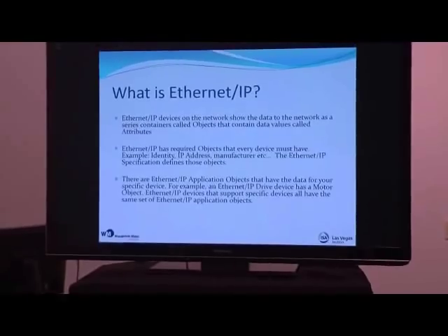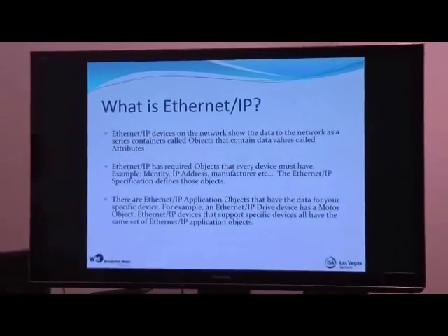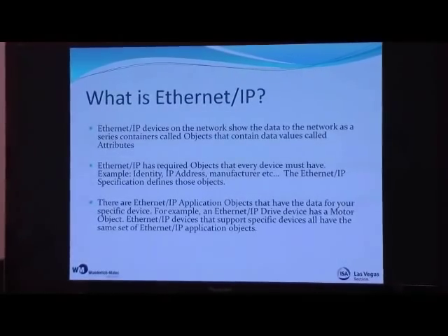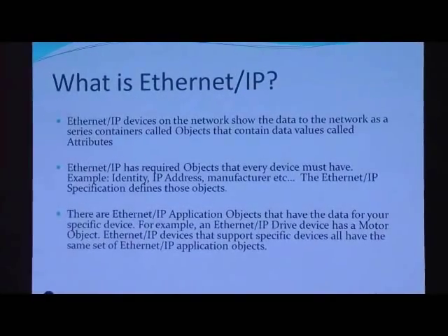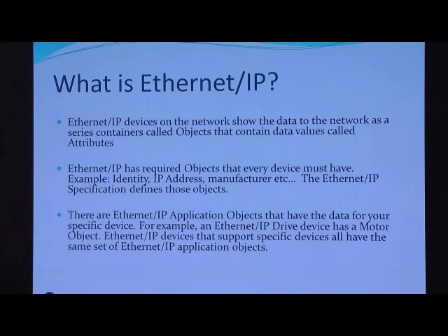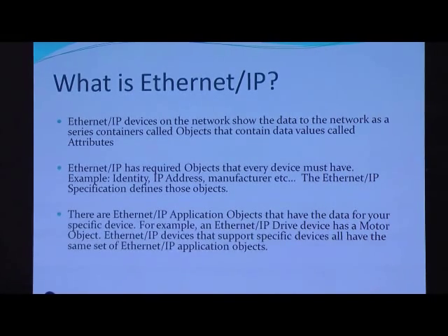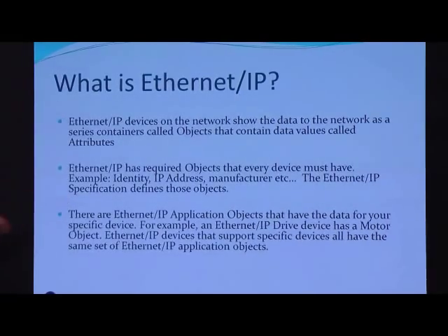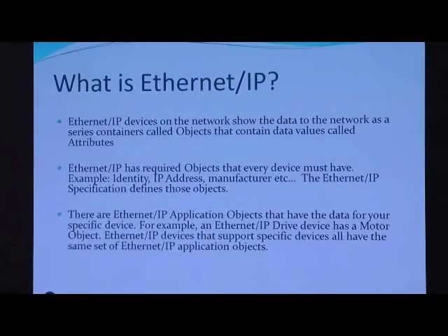Another important piece of information about Ethernet IP is that the specification requires vendors to encapsulate their data in objects. Objects contain the individual values of the device as attributes. Within a device there are two sets of objects: required objects that by specification must exist, and application objects that hold all of the process data. The required objects identify the device on the network — IP address, identity, and communication parameters — while the application objects contain all the process data unique to that device.